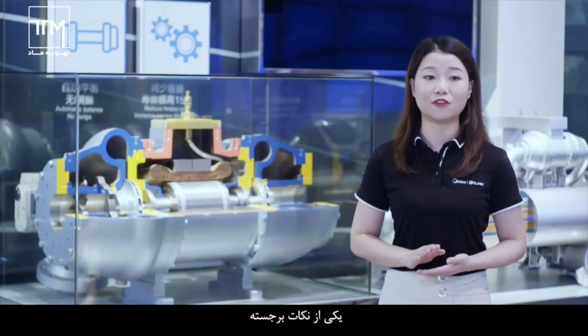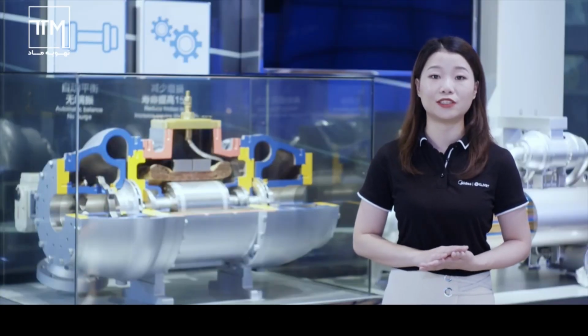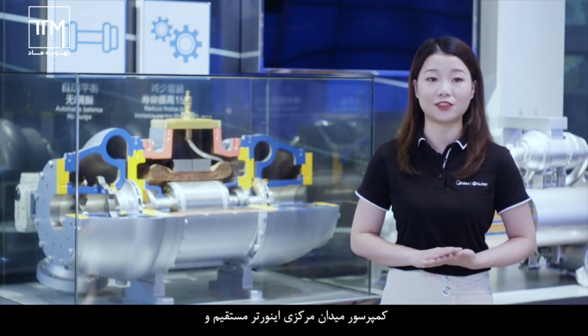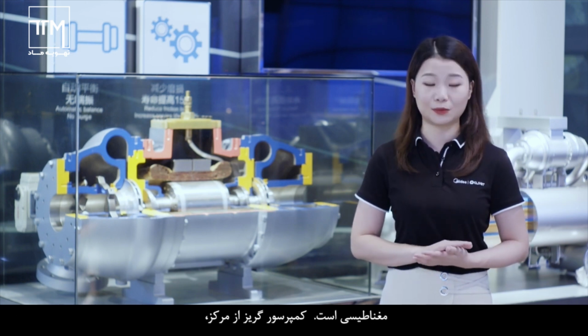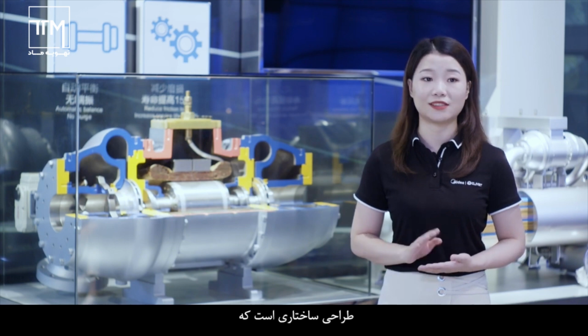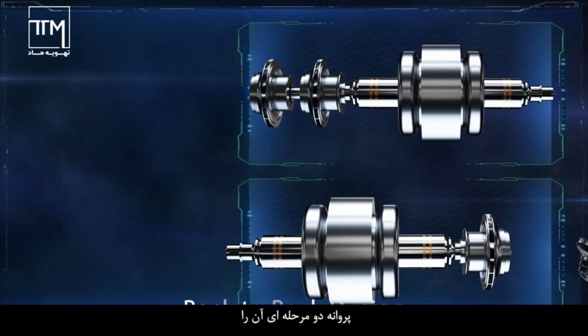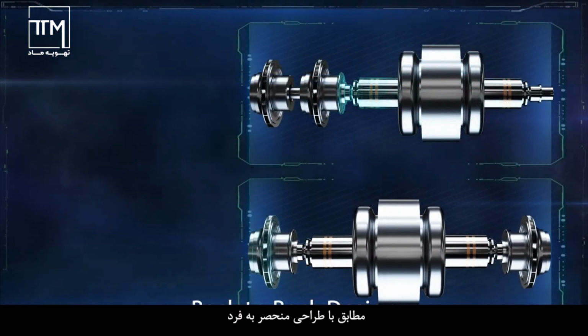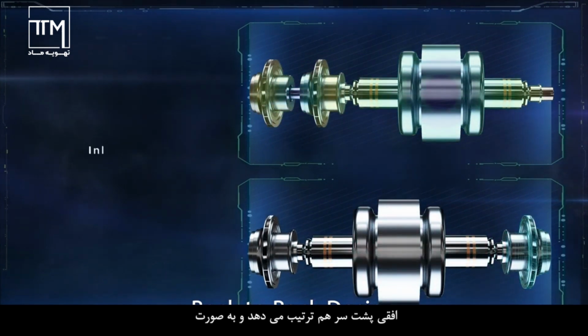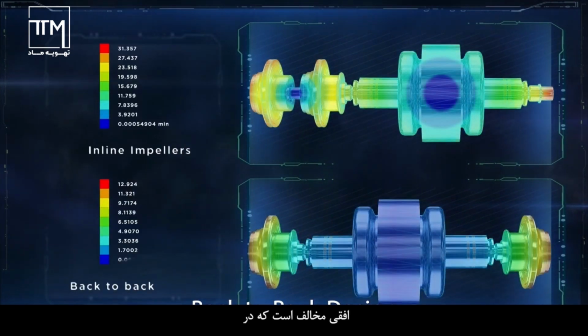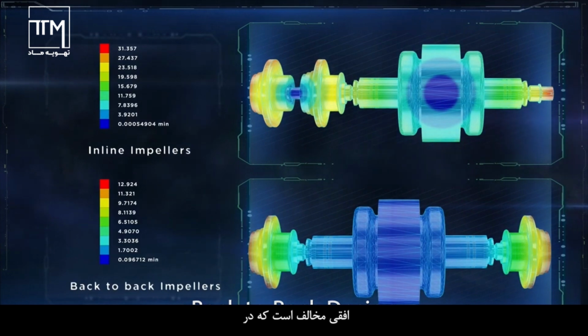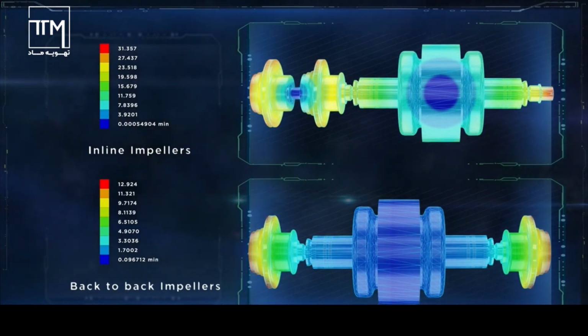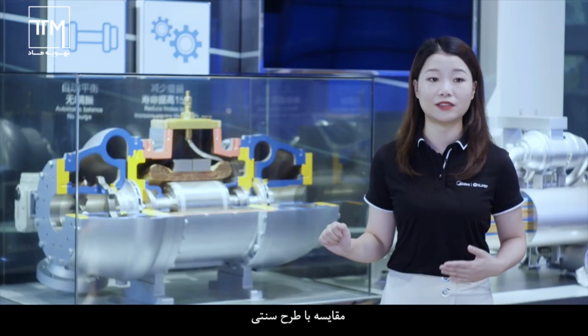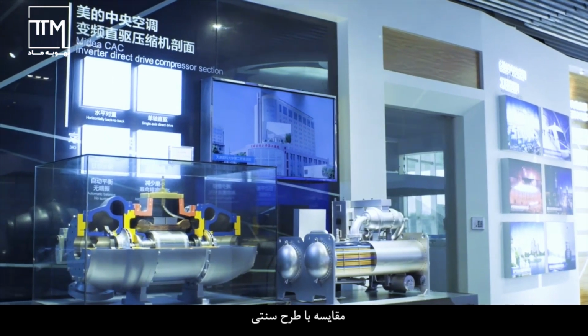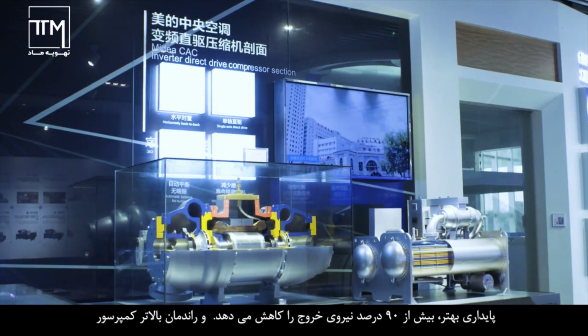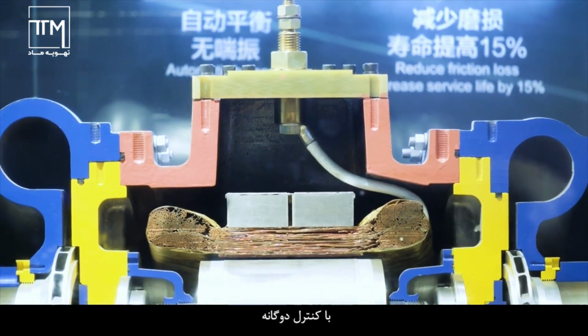One of the highlights of Midea's self-developed inverter direct drive centrifugal compressor and the magnetic centrifugal compressor is the structural design. The 2-stage impeller arranges according to the Midea's unique horizontally back-to-back design and is opposed horizontally, which reduces axial force by more than 90% compared to the traditional tandem design. With longer bearing life, better stability, and higher compressor efficiency.